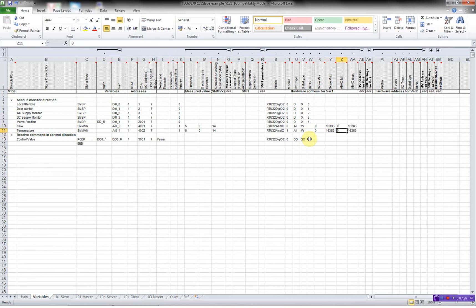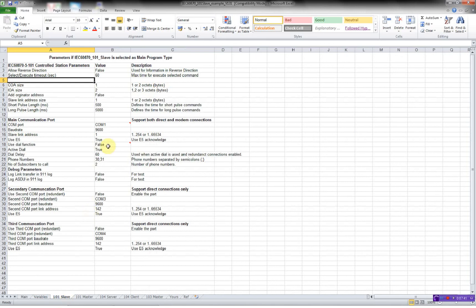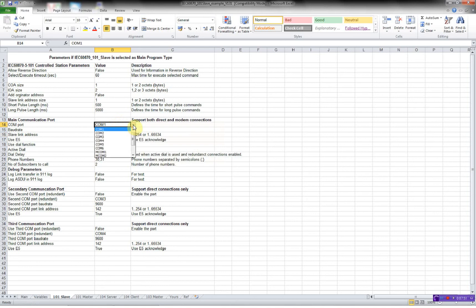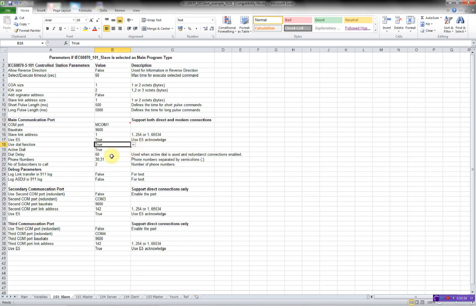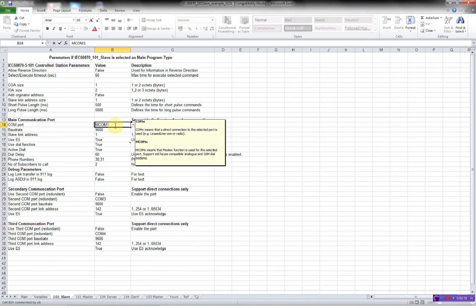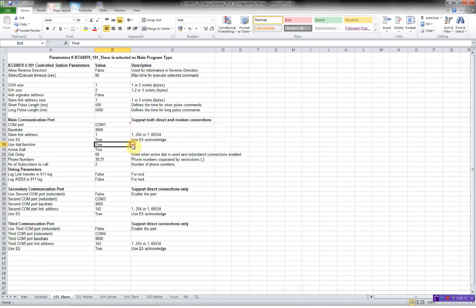So I have configured my single point, double point, measured values, and the received double command. Now I'll configure the 101 slave. Here I set my link address to one. I can decide if, for example, I'm using a modem — I can select MCOM-1, meaning a modem connected to COM-1 on the RTU32. I can also choose to use the dial function and enter the telephone number separated by a semicolon. But in this demonstration, we just have a null modem cable, so dial is set to false.